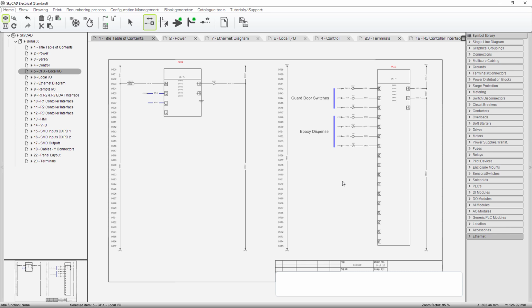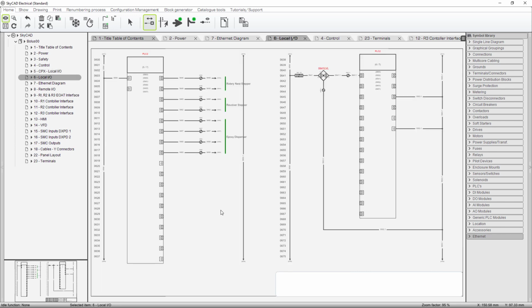The more the merrier. Okay, we're in local I/O right now, and I have 2 sheets. This one, and then I have another one that has the digital output and the analog input output. So, from my digital out, I have 2 discrete to each of the steppers. I'm not using them for anything initially because I'm doing it with Ethernet. And I'll talk about that much later, how you can do it through Ethernet. You don't need discrete. But I'm hooking them up. Guess what? If I decide I want to use one, I don't want to go find somebody that's authorized to add conductors into my panel. And remember, these run out to the stepper motor, another added complication. So you get it pre-wired in advance, and then these 4 go through a conduit to the epoxy dispenser.